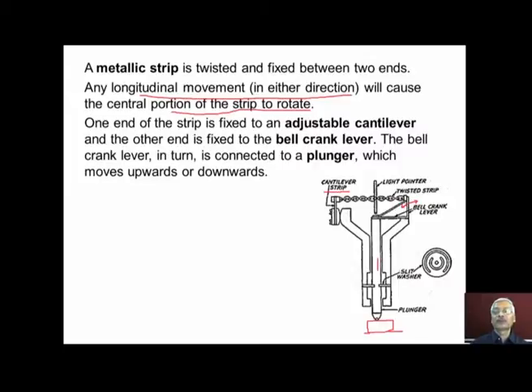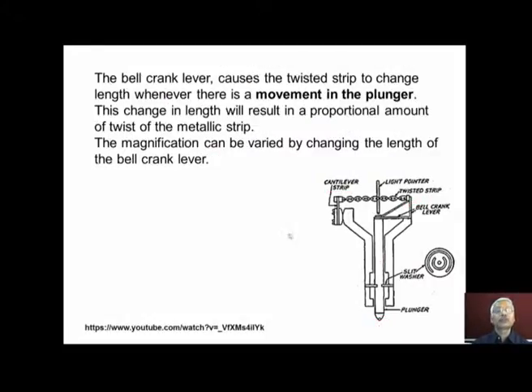Now you can see one end of the strip is fixed to an adjustable cantilever, and the other end is fixed to this bell crank lever. The bell crank lever in turn is connected to the plunger at this portion, which moves up and down when we insert the workpiece. Now the bell crank lever causes the twisted strip to change length when there is a movement in the plunger. This change in length will result in a proportional amount of twist of the metallic strip. The magnification can be varied by changing the length of this bell crank lever.